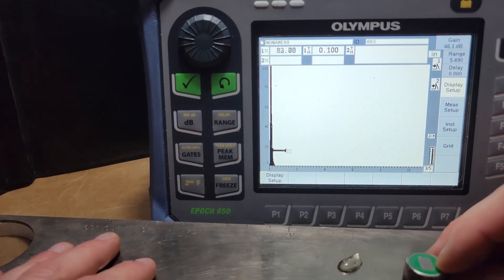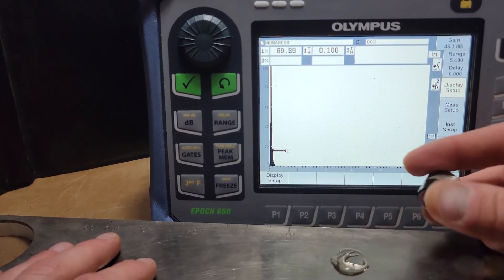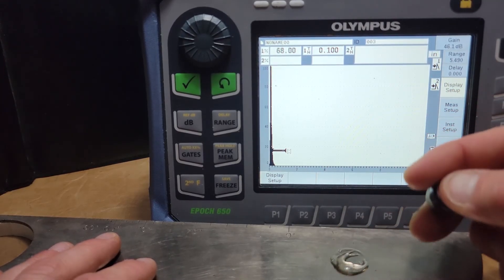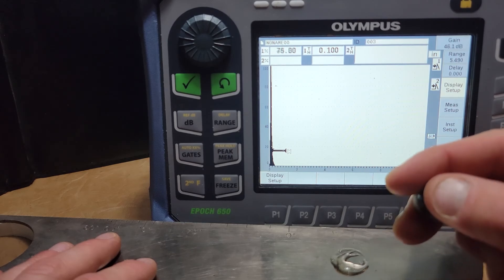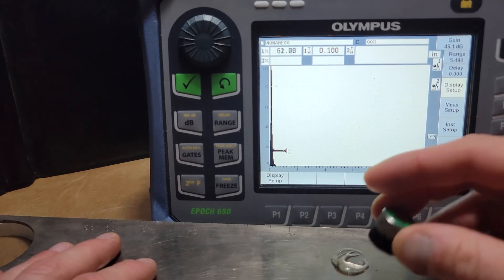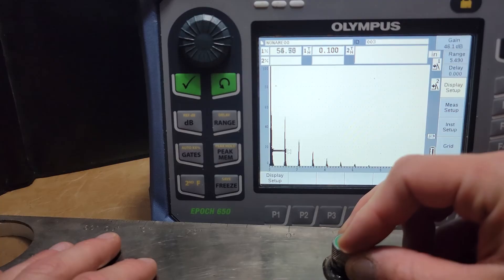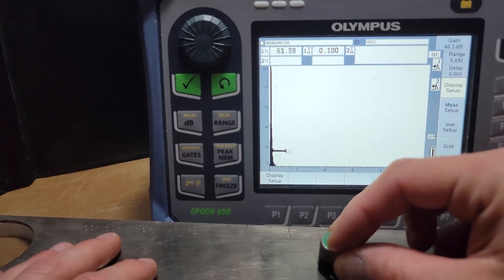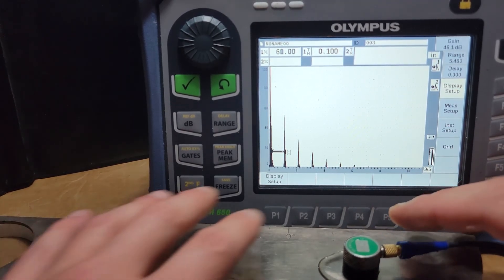First things first with this instrument, we're going to make sure that we're emitting sound and we can see a deflection on the initial pulse. Press down on the material and get some reflection echoes going.